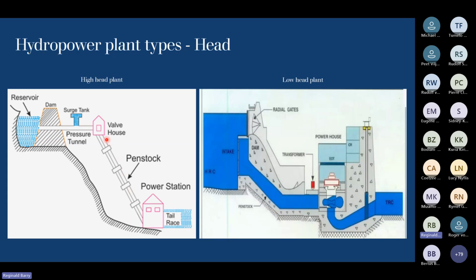Because of the very high pressure and flowing water in the penstock, if you suddenly shut down the turbine in the power station, or it trips rather from an electrical fault or network outage, then you typically have a back pressure or a transient wave in the penstock that goes through the powerhouse, through the valve house, and you need a surge tank to deal with that. The surge tank could be along the penstock, or in this case, the surge tank is for the low pressure tunnel to also deal with surge waves, hydraulic transients in the pressure tunnel itself. Okay, so that's the basics of a high head plant.